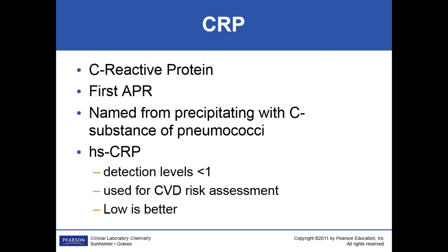And it has become so important that with our next generation of methodology, we've improved it so we can go better on the low end. On our biuret methodology, 1.0 grams per deciliter was the low end. Well, maybe we need to know, is it 1.3 or is it 0.5? That becomes a very significant area, and with our biuret, we can't detect that. We can't give them good answers because our sensitivity is not good enough.